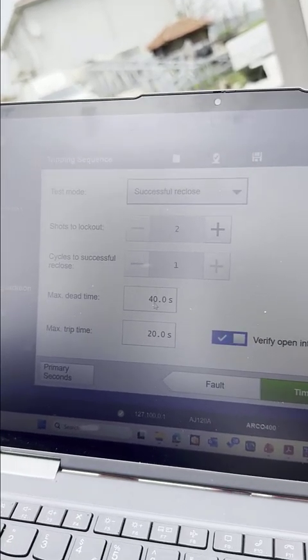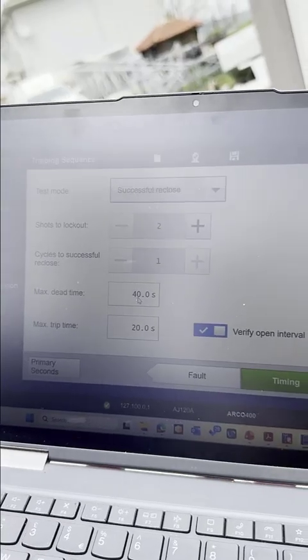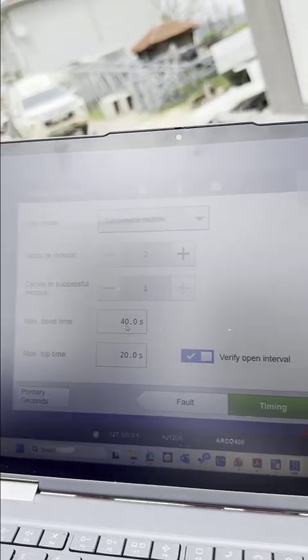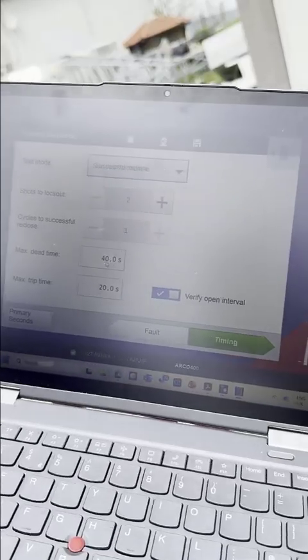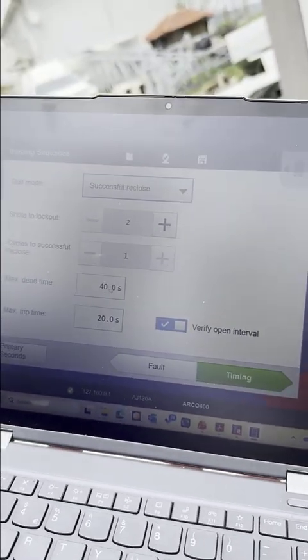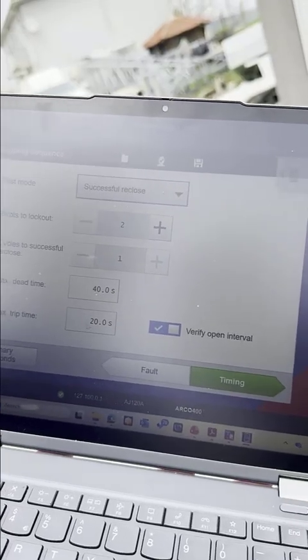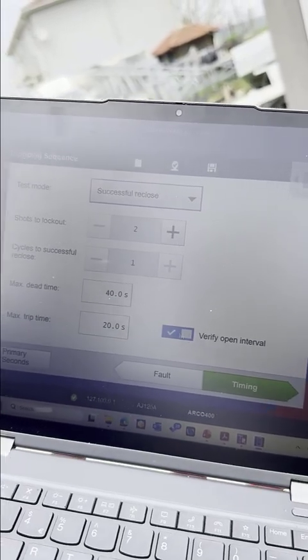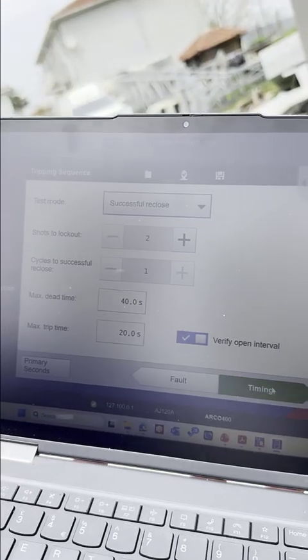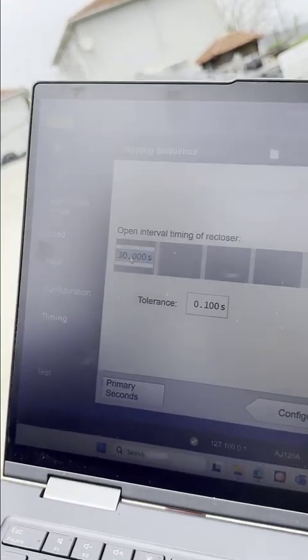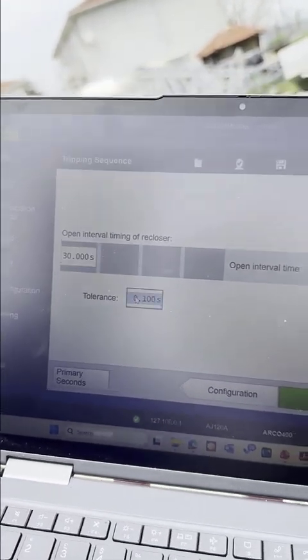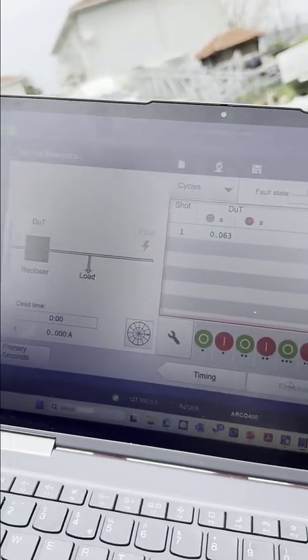Here the maximum dead time is 40 seconds, which should be longer than the expected reclose time, which is the expected dead time we have in the parameter setting equal to 30 seconds. So 40 seconds is more than enough. Here the maximum trip time is 20 seconds, and you also have to enable the verify open interval to measure the dead time, which is expected to be 30 seconds, with a tolerance of 100 milliseconds. Then you can go for test. Then you can start your test.